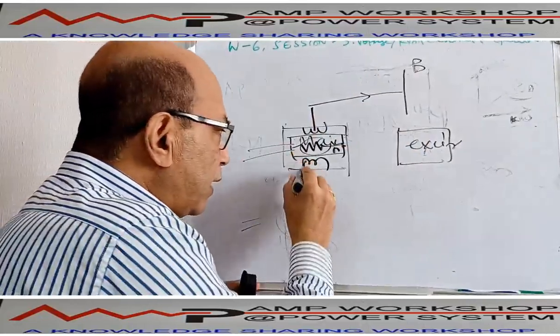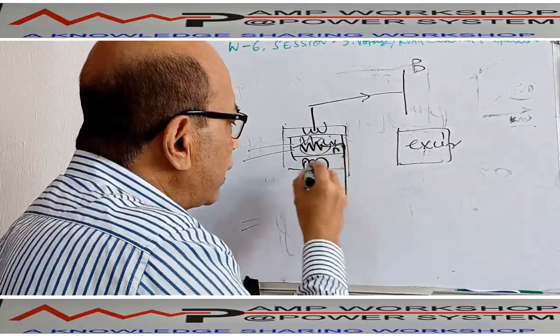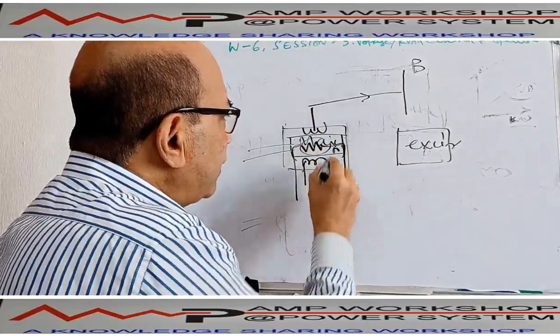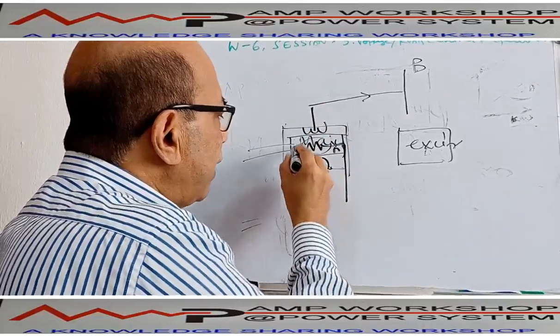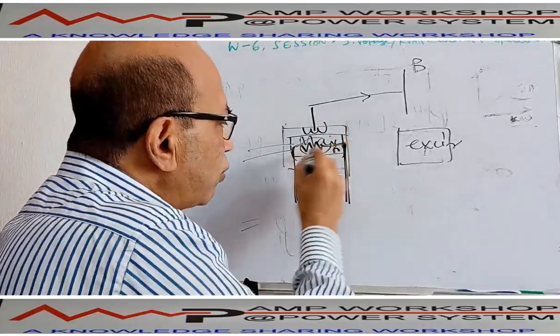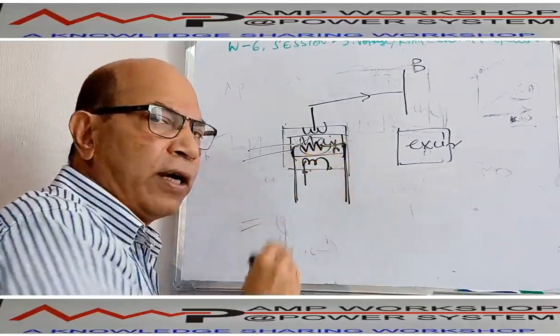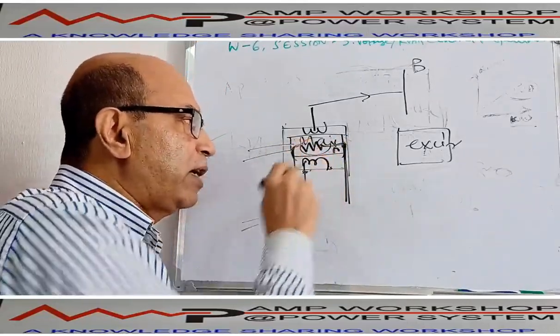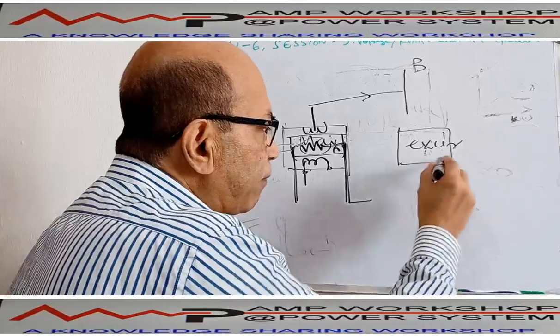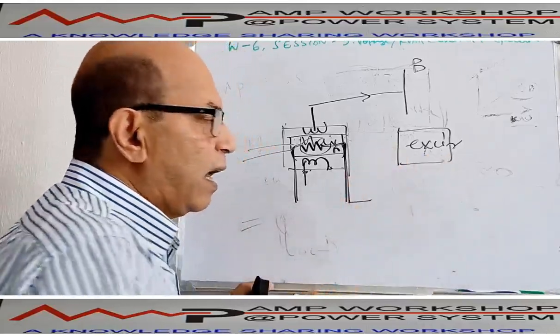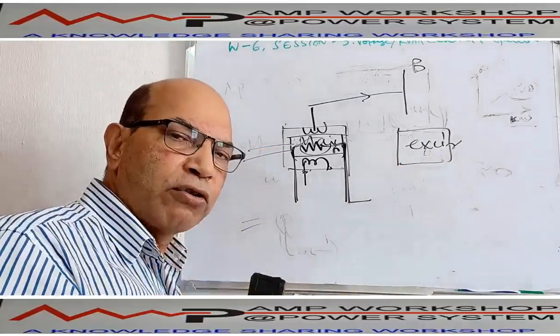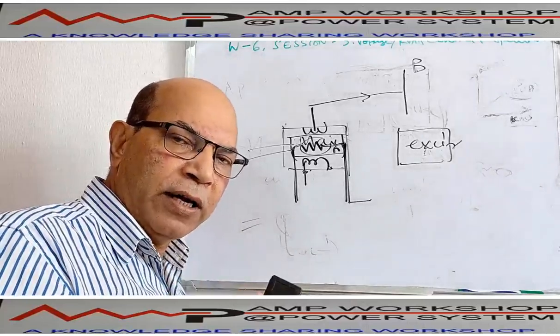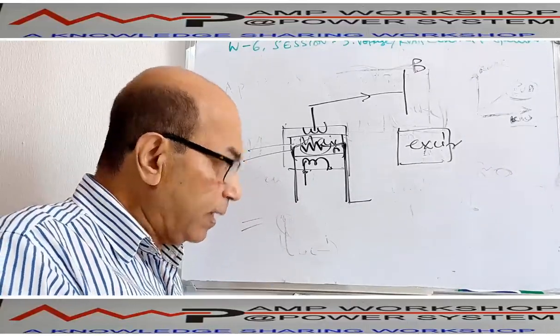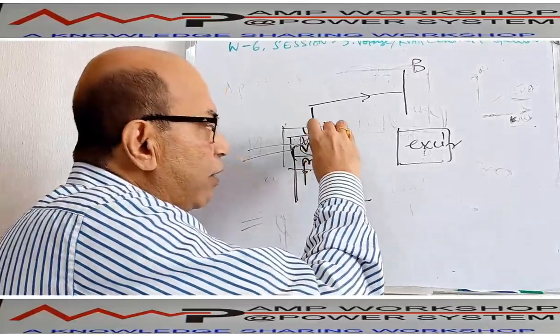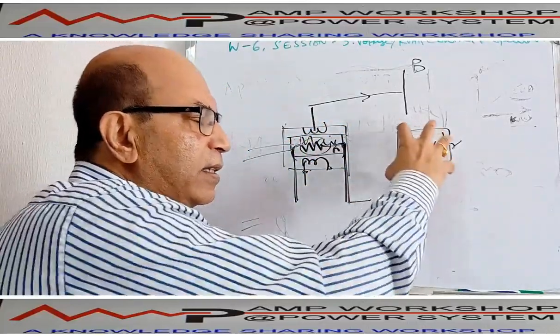This is called the rotor winding. This is one phase, this is another phase, and this is your rotor winding. This rotor winding is a DC winding, and it is getting power from the exciter. How is this exciter working? The exciter also has two windings, one called the armature winding and the other called the field winding. But here, the rotor winding or field winding is rotating, while in the exciter it is reverse.